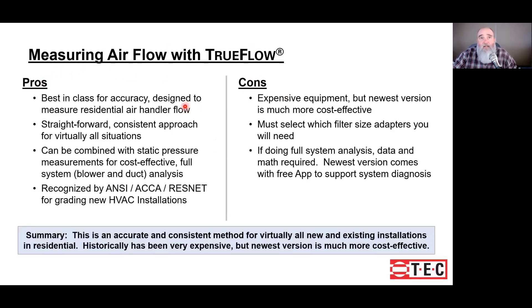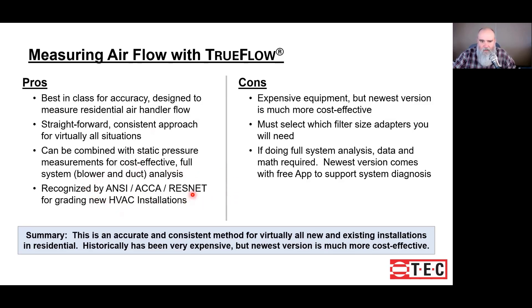There are lots of pros and cons with this device. The biggest pro is airflow — it is a very simple tool to measure airflow. When we use it with the TrueFlow app, it's not only going to measure airflow but it's going to point to deficiencies in the system or confirm that things are as they should be. Essentially, we can use it for grading our HVAC installations, whether for our own purposes or for compliancy requirements. All the big three recognize this as a methodology.